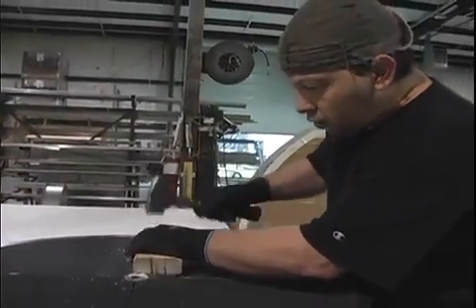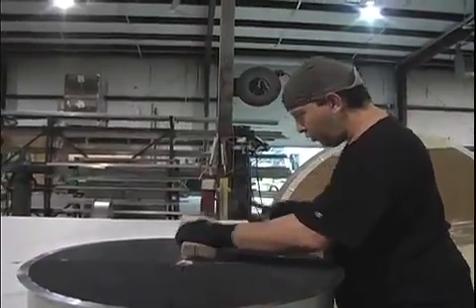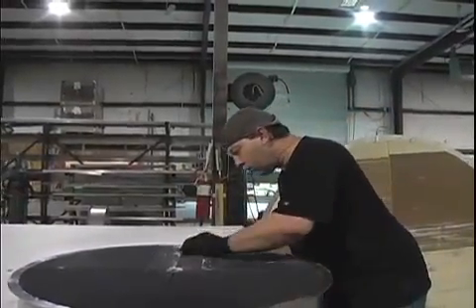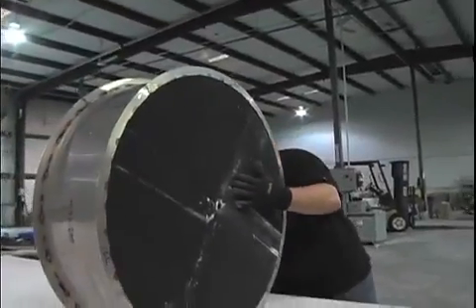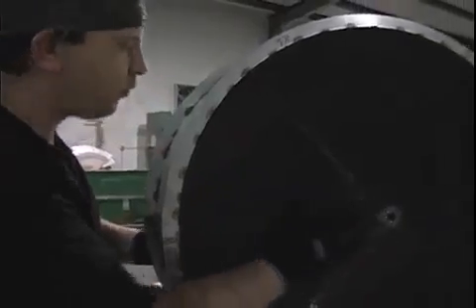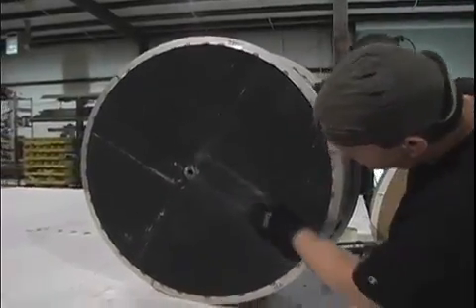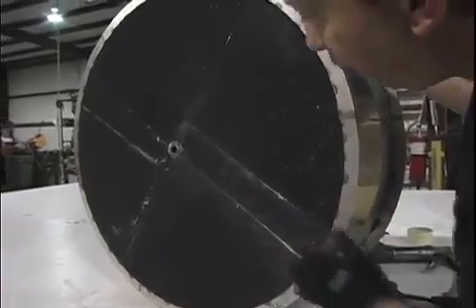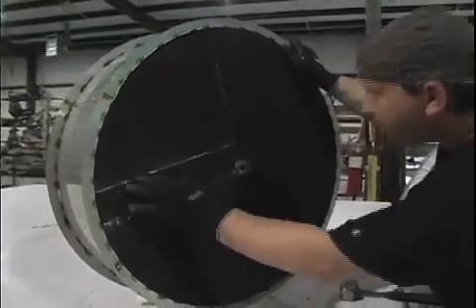Just make sure to tap it down evenly. Make sure that we're good and flush on both faces and adjust the media over. I would also recommend putting a small bead of RTV right there just to seal that seam off. Now that the segment is installed, blow it out with compressed air and apply a face coat.